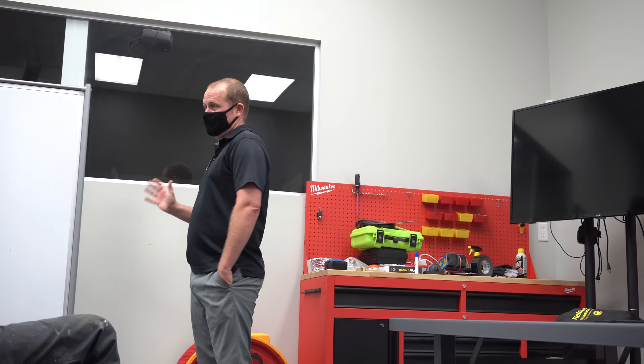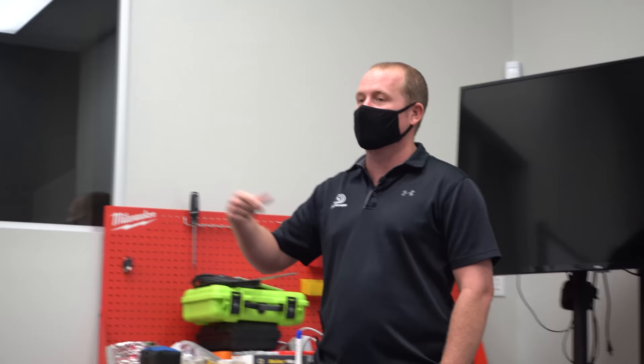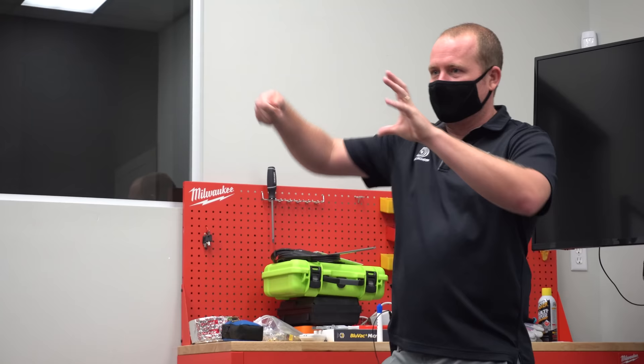For blower wheels, obviously the best way is to pull them out — they're generally not that hard to do. Pulling out housings is good practice because you can get the housing clean and also clean the motor end bell. When cleaning a motor end bell, don't spray any liquid on electrical devices. You have to take the motor off the blower wheel in order to clean it. You can also clean the motor end bell separately — sometimes the blower wheel isn't dirty but the end bell is, since blower wheels use open motors. You can wipe it off with a rag, use contact cleaner, or use nitrogen to get the stuff off. It's good to have a shop vac present so you clean up as you go.